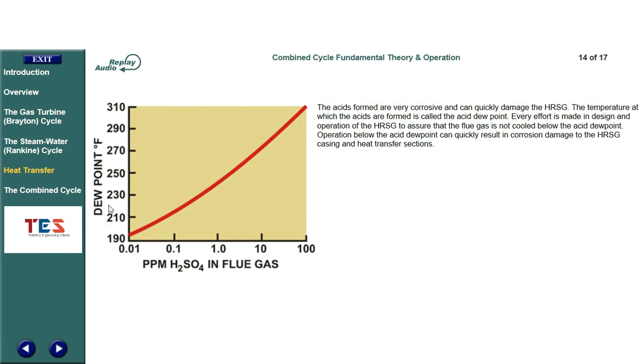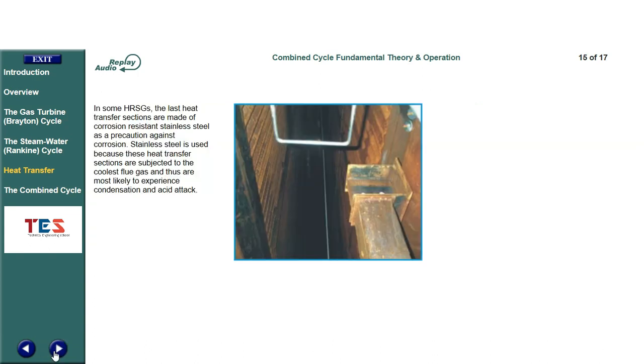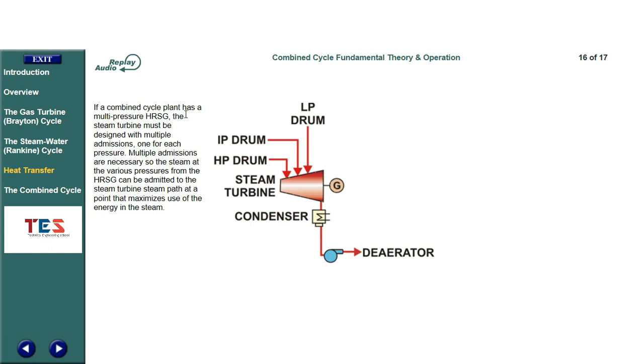The temperature at which the acids are formed is called the acid dew point. Every effort is made in the design and operation of the HRSG to assure that the flue gas is not cooled below the acid dew point, as operation below it can quickly result in corrosion damage to the HRSG casing and heat transfer sections. In some HRSGs, the last heat transfer sections are made of corrosion-resistant stainless steel as a precaution, since these sections are subjected to the coolest flue gas and are most likely to experience condensation and acid attack.